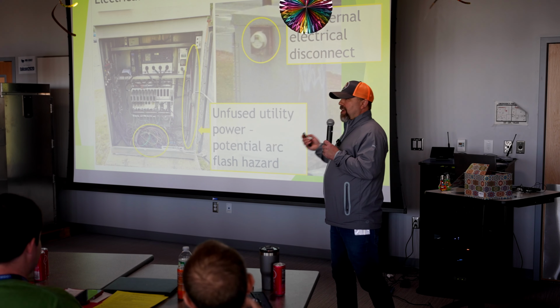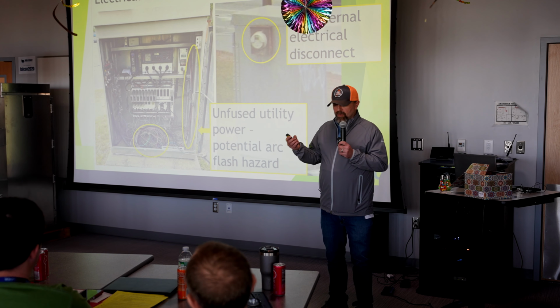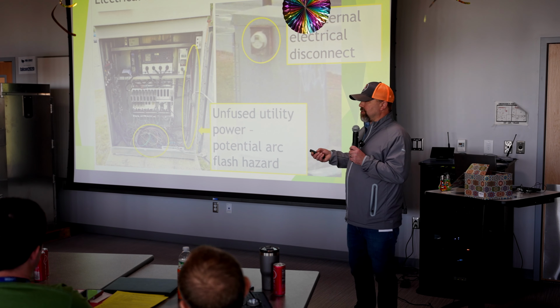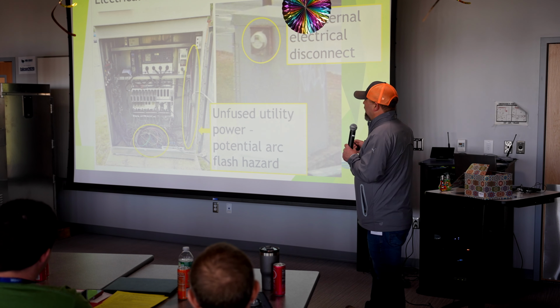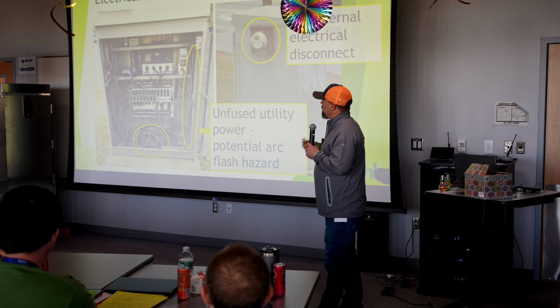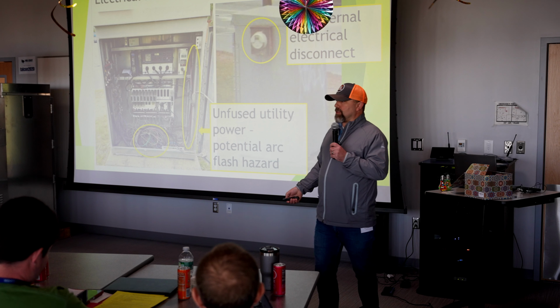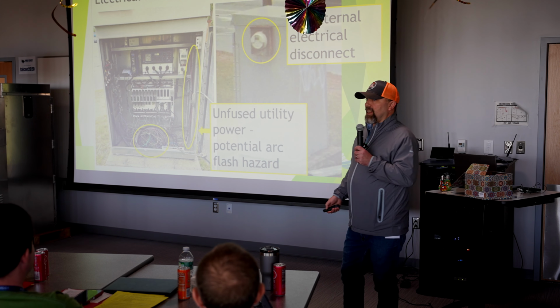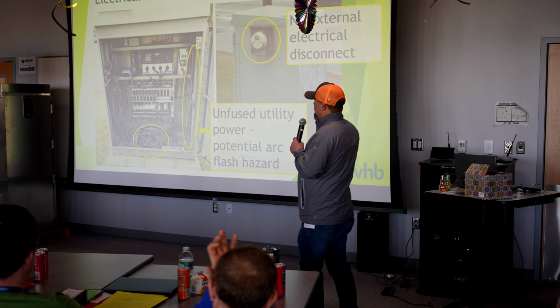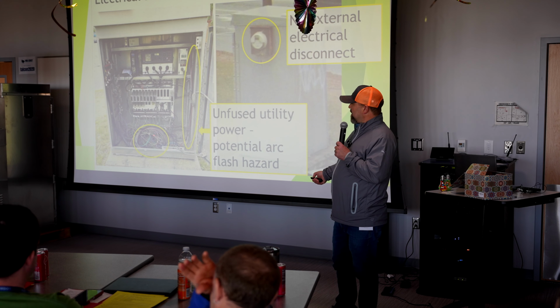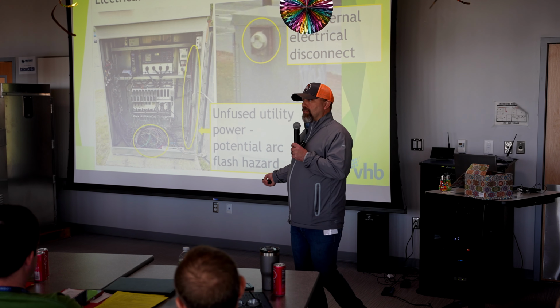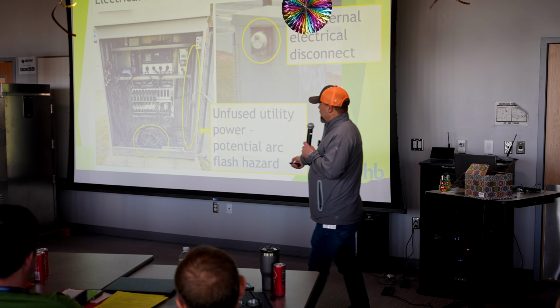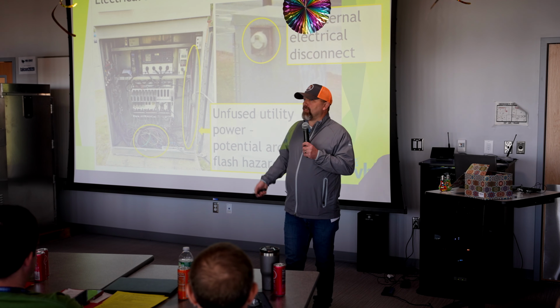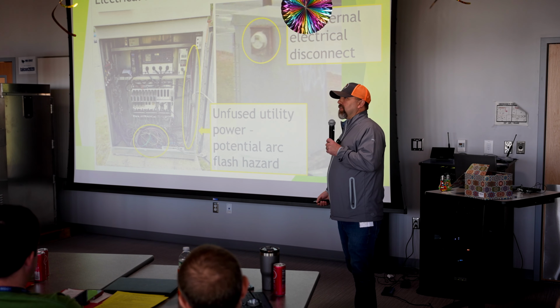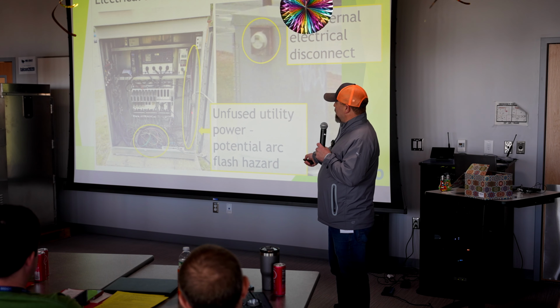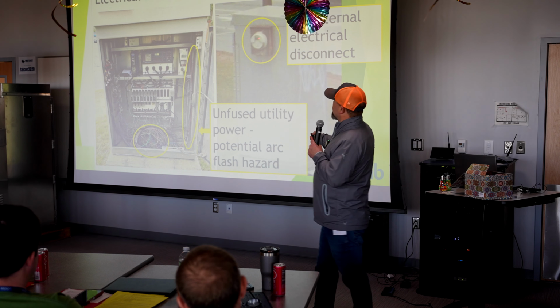I'm just going to move on to changes in requirements for electrical services. I've always felt that this was an interesting setup, because when I got into the industry in 2001, the way that the traffic cabinets were installed with the electrical service, this is pretty standard operating procedure. The conduits coming from the service pole come up into the cabinet. It wasn't uncommon to have a service loop, say 15 feet, coiled up. And then you're literally running the wires that are coming down from the utility, directly from the transformer that's up on the pole, into your cabinet and running up the side and then into the back of your meter trim right here.